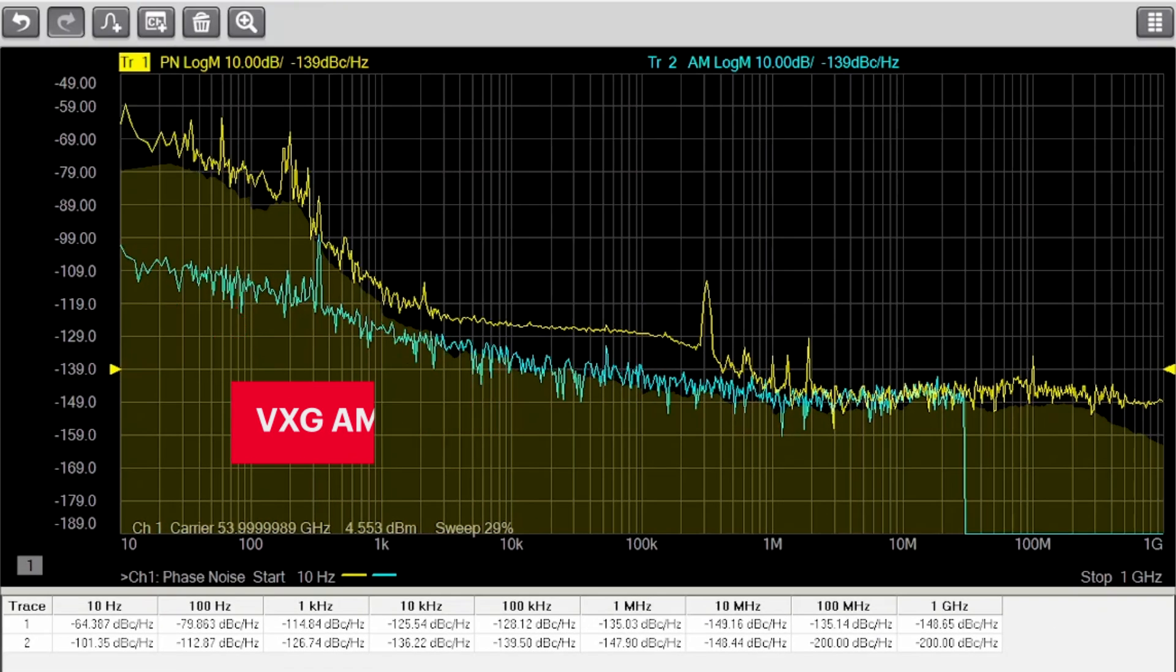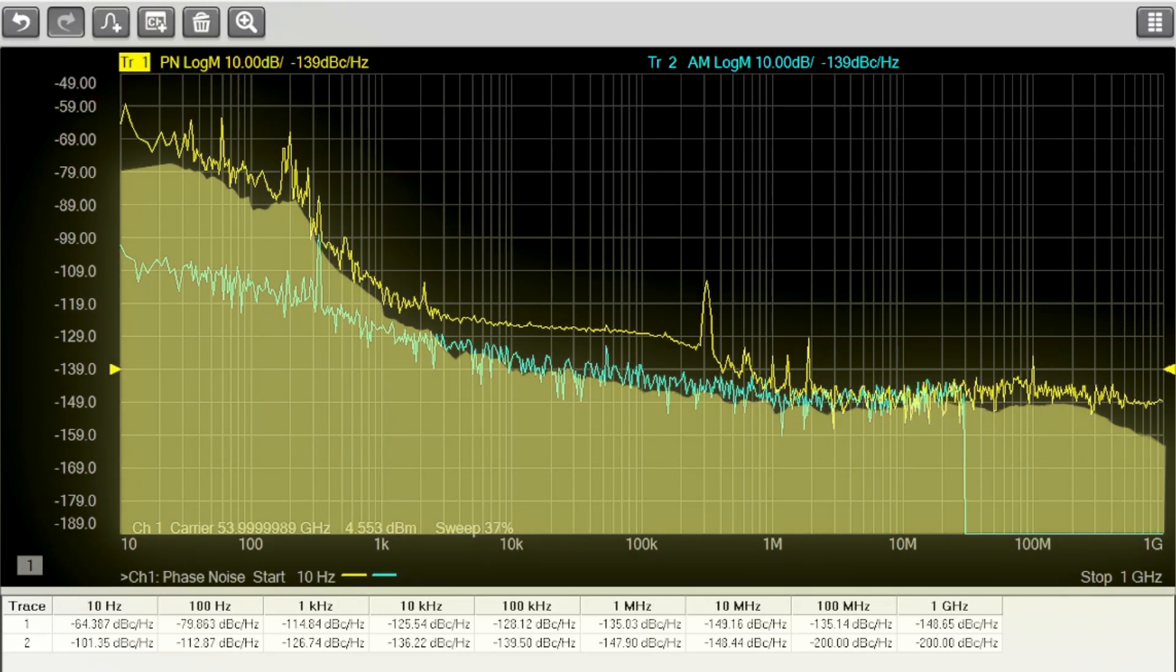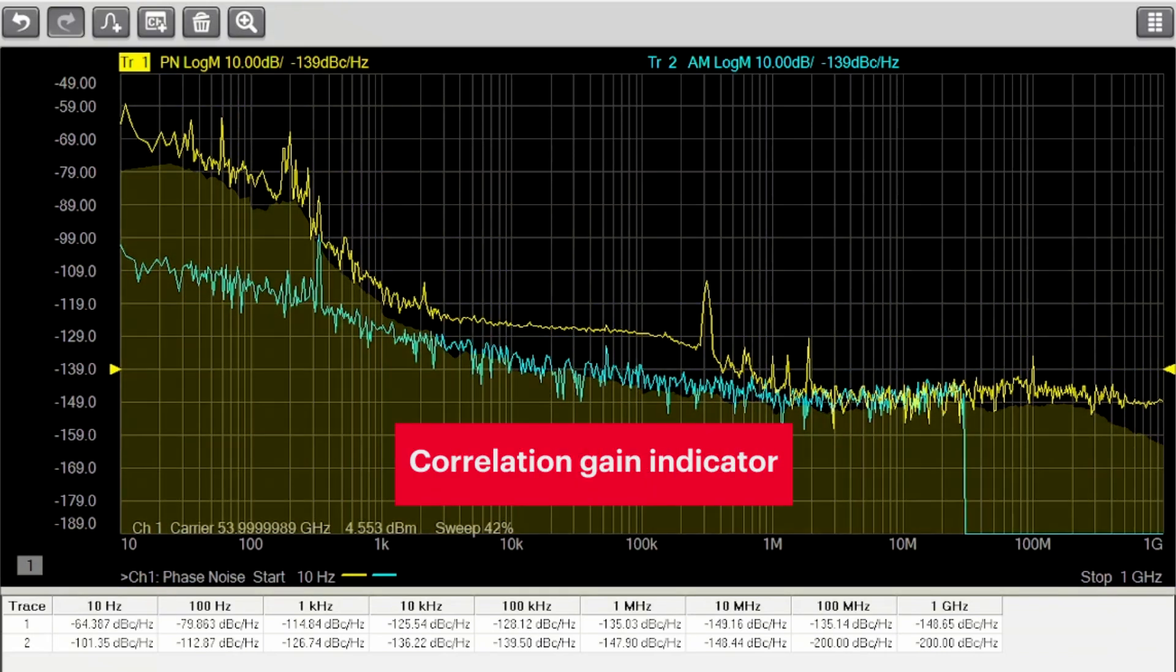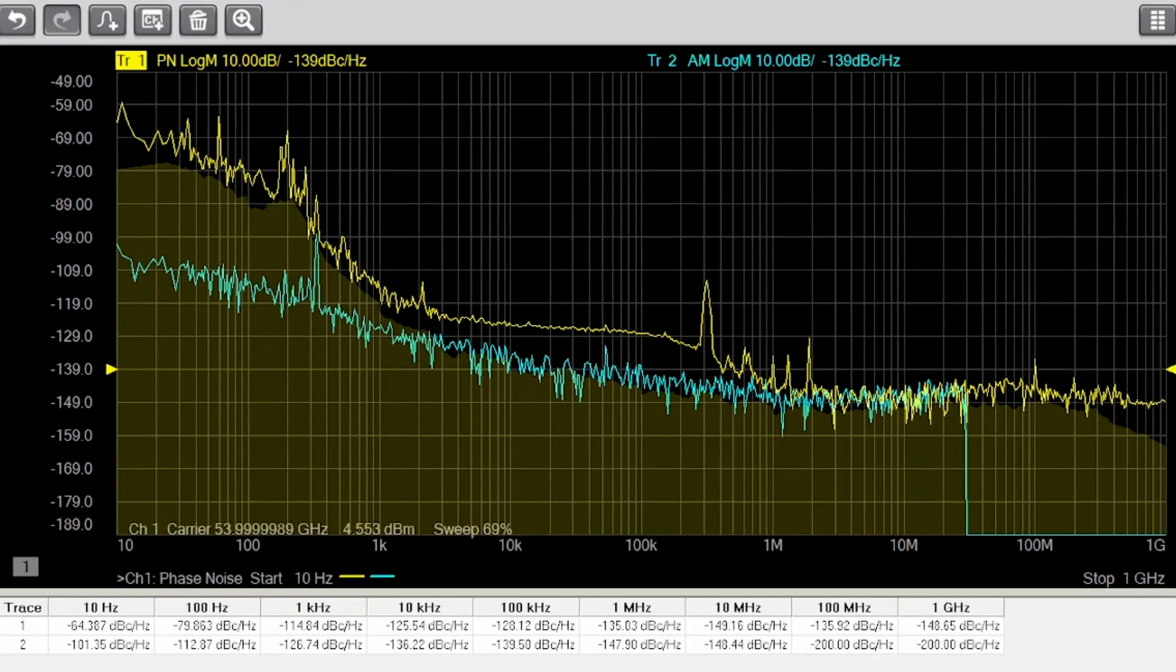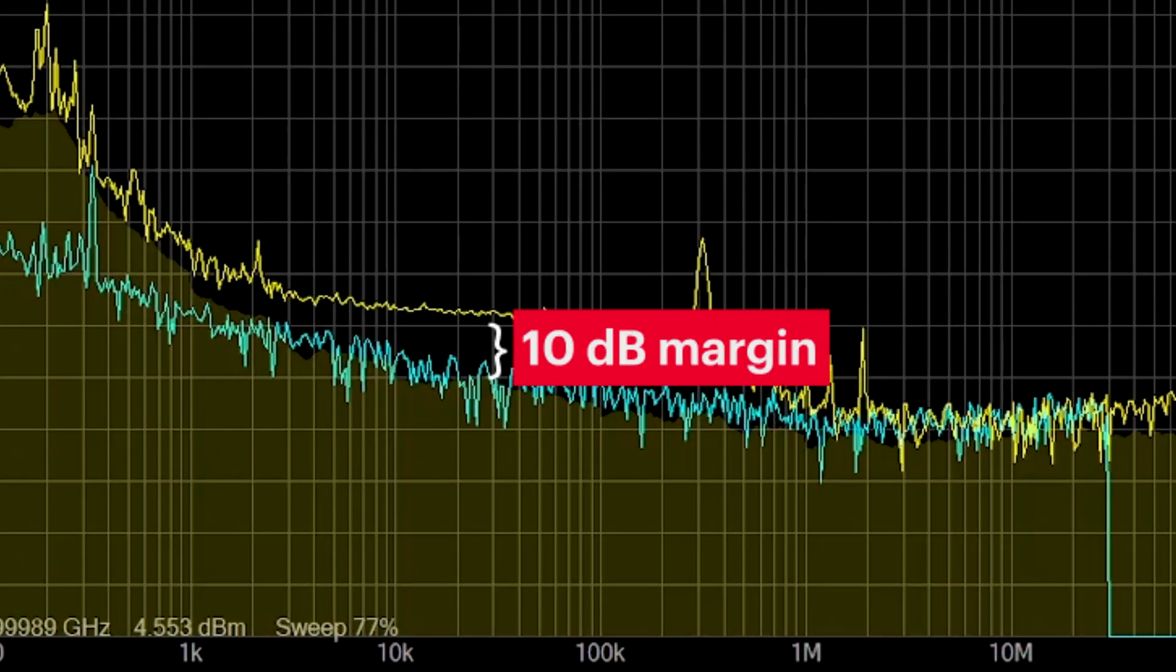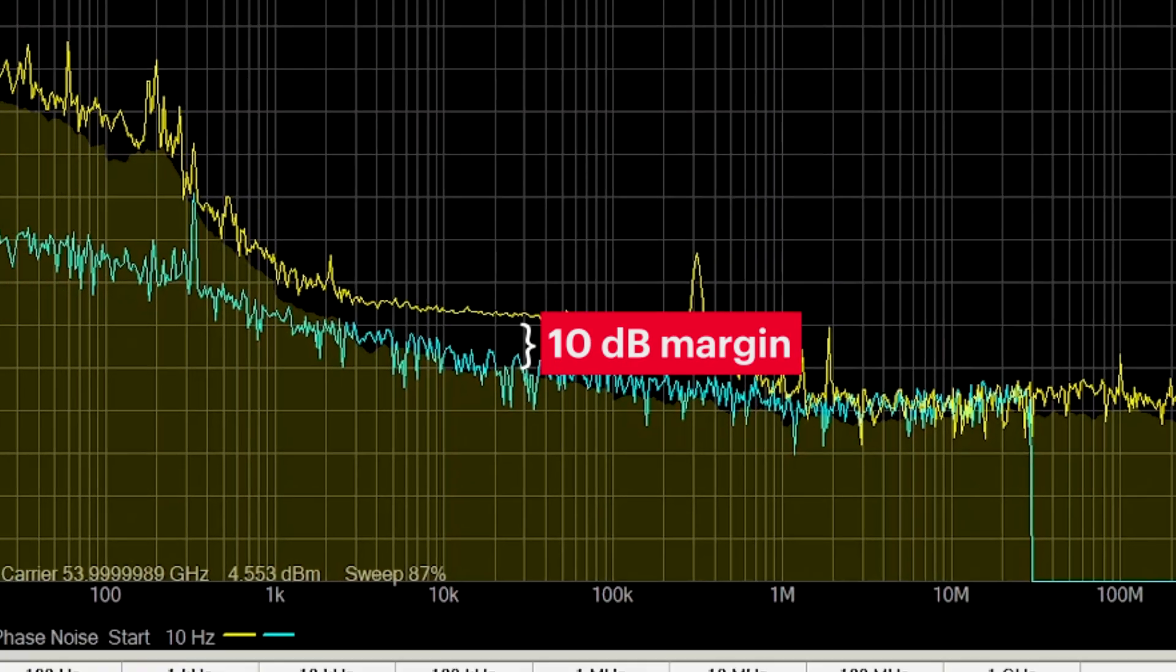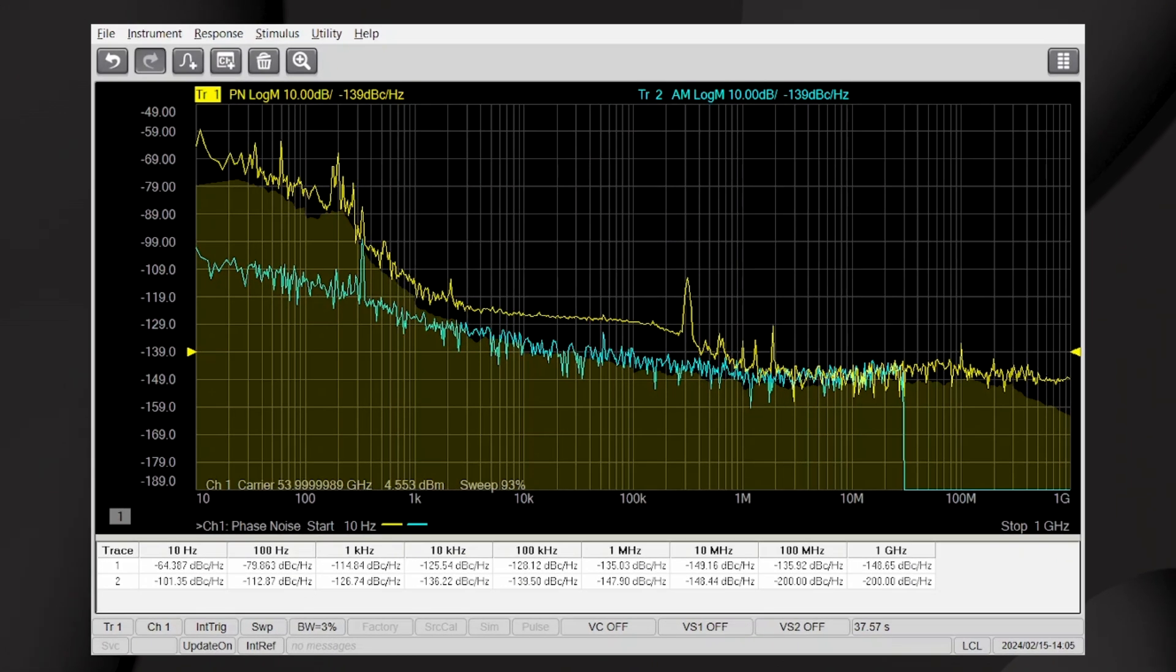Below the trace, we can see a translucent shaded area that we call the correlation gain indicator. The correlation gain indicator shows us the improvement in measurement system sensitivity that we get from a given amount of correlations. Ideally, we would have 10 dB of margin between the solid yellow trace and the correlation gain indicator area to ensure that we are measuring the VXG's actual phase noise.